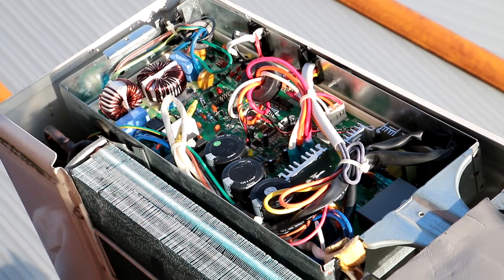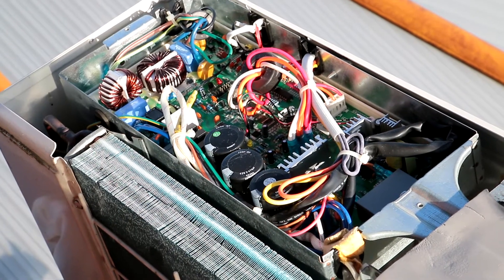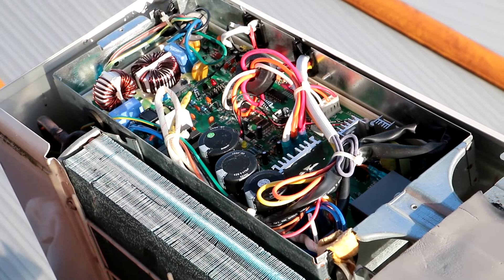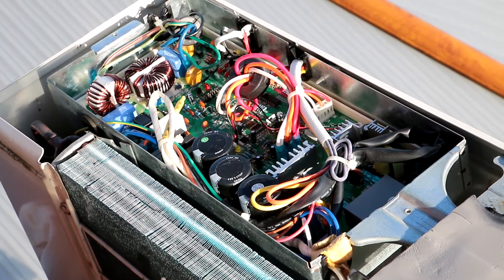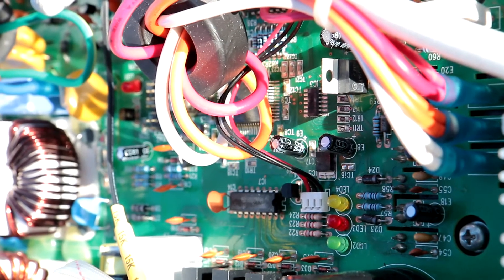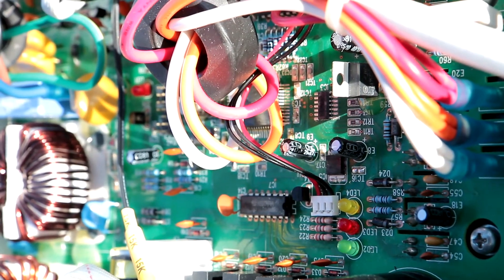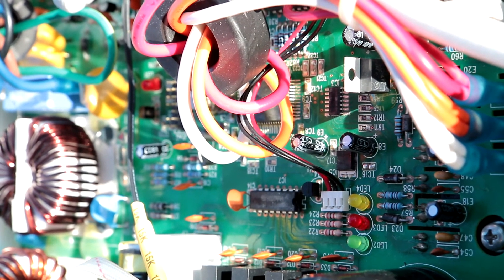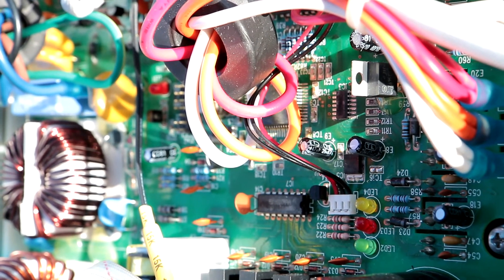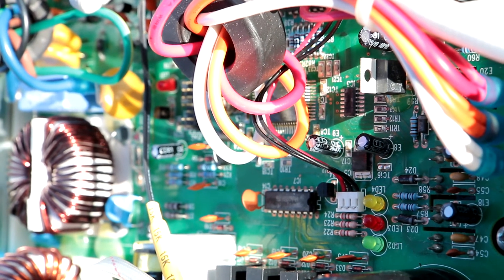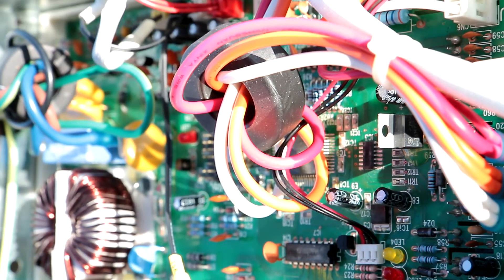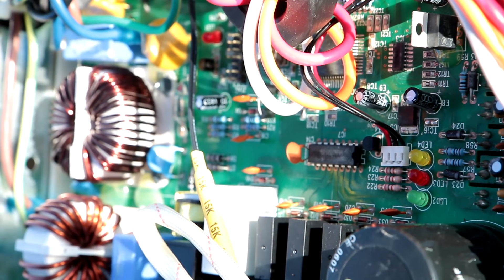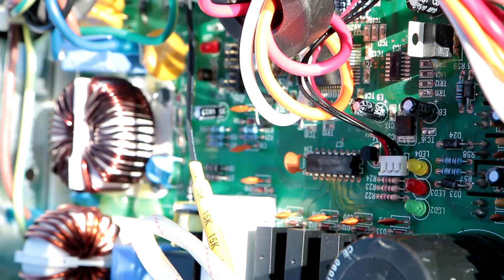You can see the status LEDs in the bottom right hand corner there. The green one, LED two, flashes when there's communication between the indoor and outdoor units. I have no idea what the red LED which is LED three means or the amber which is LED four.